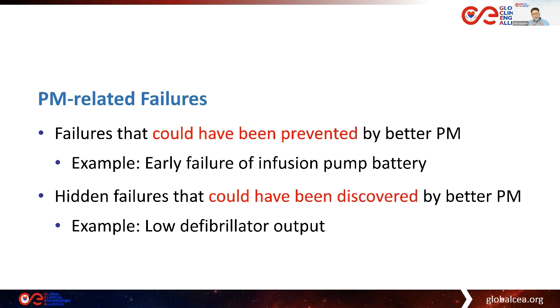The other aspect of PM-related failures is hidden failures that could have been discovered by better PM. For example, a low defibrillator output, we discover that by coming around with our defibrillator tester and measuring the output compared to expected values. If it comes out short, that's typically hidden from the user, and it could only be discovered by us coming around and doing that actual inspection.